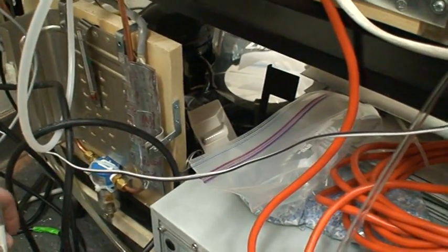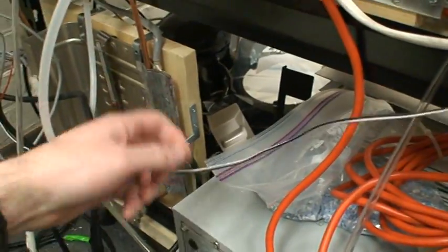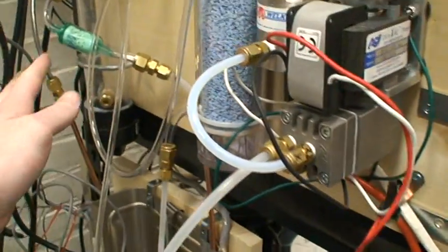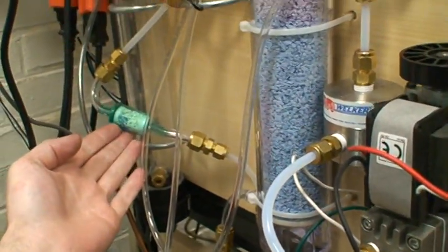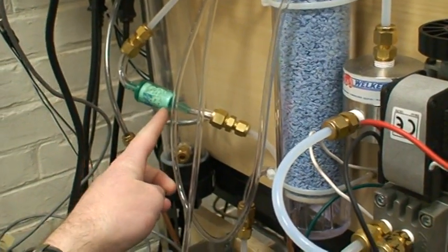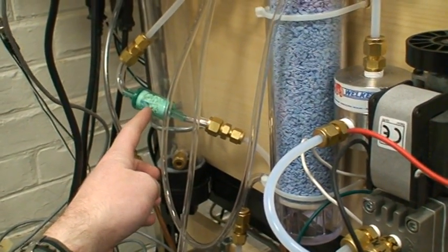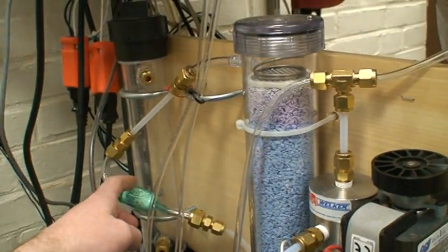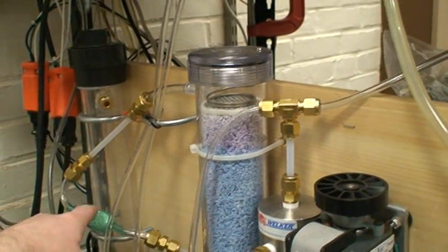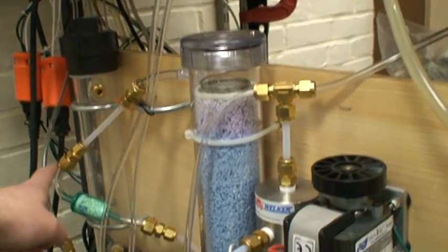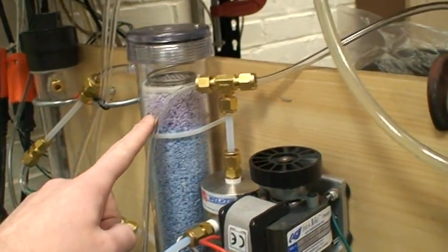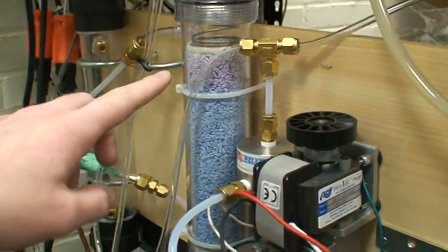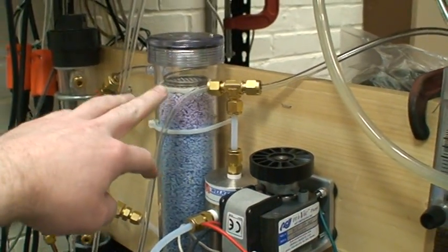Once it goes through the half of the heatsink, through the filter, up through the second half, it goes through a Balston acid filter, so that collects any excess acidic vapors that have come through the combustion process, or generated by the combustion process, I should say. Then we come up and go through a desiccant. So we have a Drierite. This is a commercial Drierite filter.